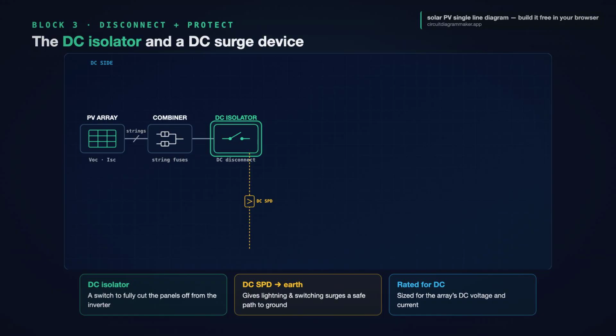Right next to it, we add a DC surge protection device, an SPD, tied to earth. Solar arrays sit out in the open, exposed to lightning and switching surges, and the SPD gives those spikes a safe path to ground before they reach the inverter. Isolator to disconnect, SPD to protect. Both belong on the DC side of the line.